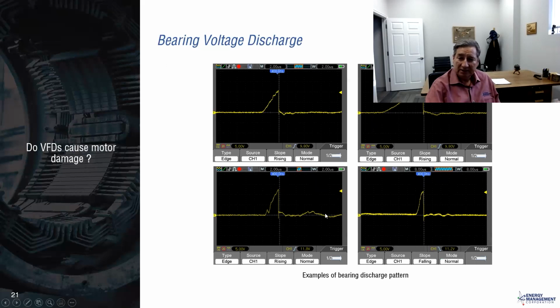Here's a couple of other oscilloscope graphs. This was another vertical hollow shaft, which seemed to have more propensity to this sometimes. You can see that this built up a little bit longer until it hit that. This was a lot longer. This was a very short one, but those are classic waveforms from an oscilloscope. You see that ring on your oscilloscope, and you've got to expand in on that initial rise time. I was going to say that the rise time is associated with dV/dt, but really this is your shaft voltage, so it's not really associated with the rise of that first coil of the electrical winding.